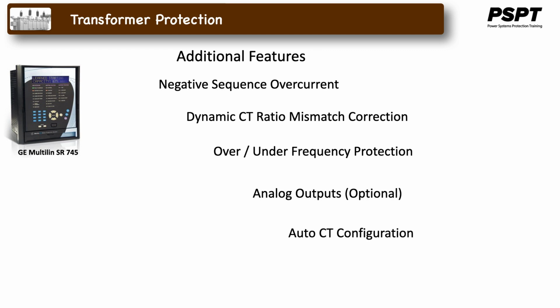All feed-in CTs are connected in a Y configuration for simplicity. Then all phase and magnitude corrections, as well as zero sequence current compensations, are performed automatically based on a choice of over 100 transformer types.